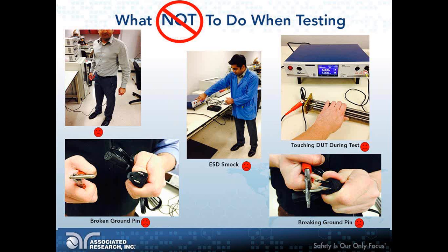In the picture in the center, we see one of our other applications engineers, Bishan, posing wearing an ESD smock. Again, electrostatic discharge does not go well with high voltage testing. The operator should not be grounded at any point, because then all you're doing is providing a path for any discharge on your product to flow through your body instead of the return lead or return connection of the test.